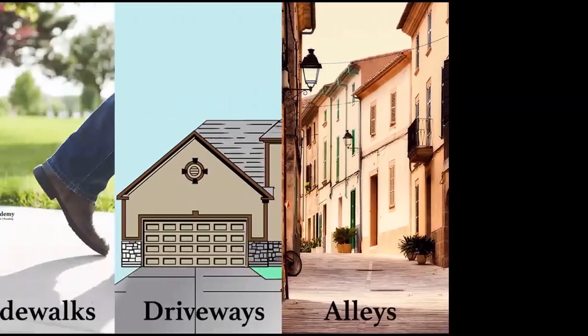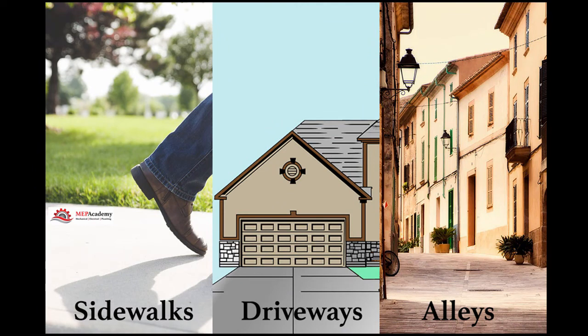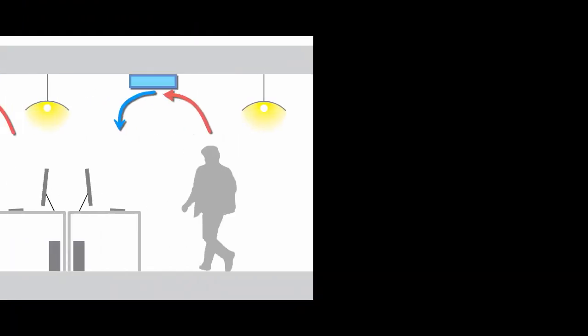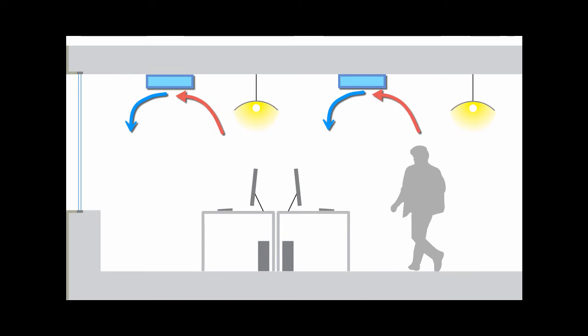Some locations where you cannot terminate condensate include public ways like sidewalks, driveways, and alleys. Excluded from these code requirements are non-condensing types of equipment like radiant cooling panels, which are designed to prevent condensate from occurring by keeping the temperature of the chilled water above the dew point temperature or vapor pressure of the surrounding air. These systems are designed to operate in sensible cooling only modes, so you shouldn't have any condensate — they're excluded.